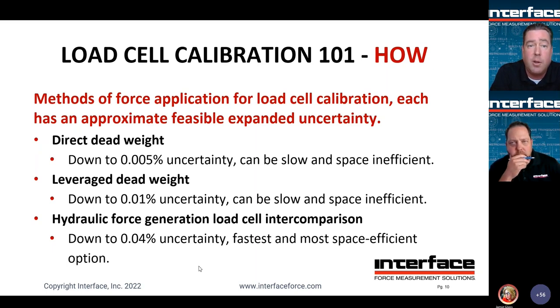Another technique would be leveraged dead weight, where they take a dead weight stack and apply it to a lever arm. This offers uncertainties down to 0.01%. This does still share some of those same drawbacks that the dead weight has, in that it can be slow and it can be space inefficient. Again, we're dealing with mass. It does take room. Hydraulic force generation and load cell intercomparison is down to 0.04% uncertainty and is the fastest and most space efficient option. At Interface, that's primarily what we do, the hydraulic intercomparison. Slide, please.